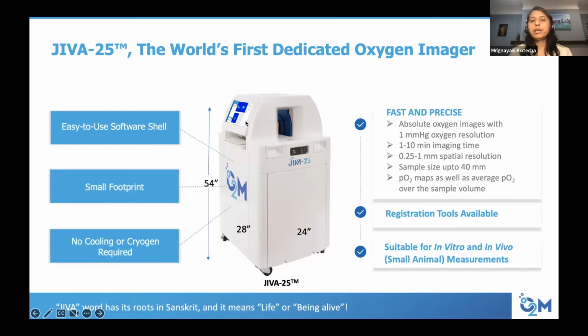It's a small footprint. You can plug it in any corner. No cooling cryogen is required because we are using a permanent magnet. We have registration tools available currently on MATLAB, but slowly we will transition them to the main software of the instrument. And one advantage I would say, Marty mentioned the easy access to the magnet and animal, but we also have vertical access, because many times biomaterial measurement needs vertical access. Simply put, calibration also needs vertical access. So the instrument is accessible both horizontally as well as vertically.